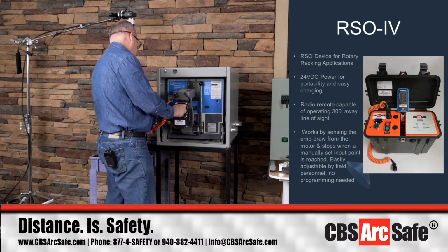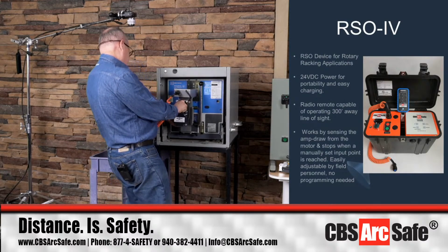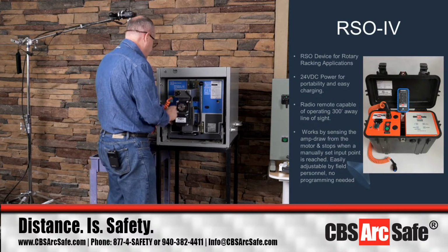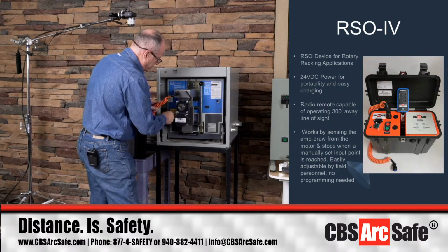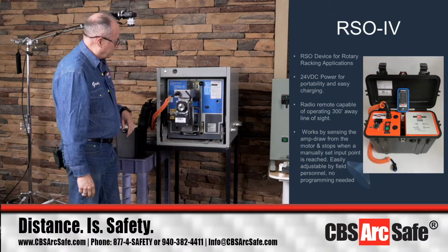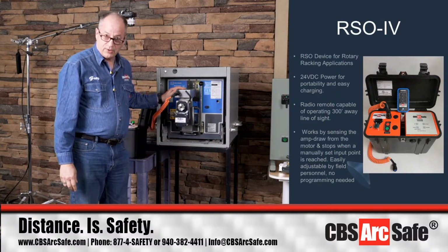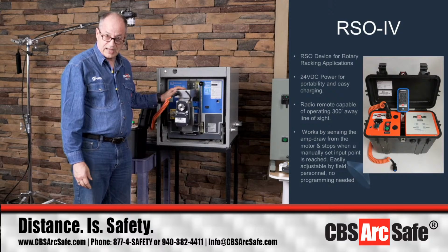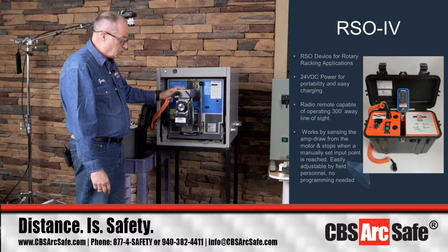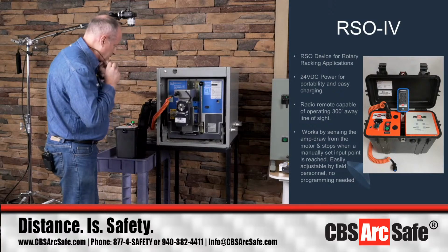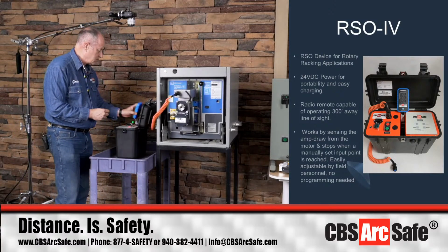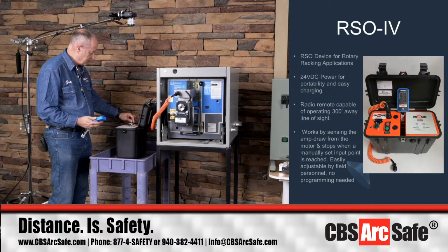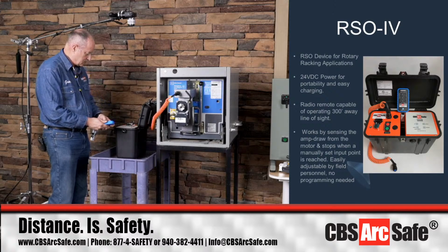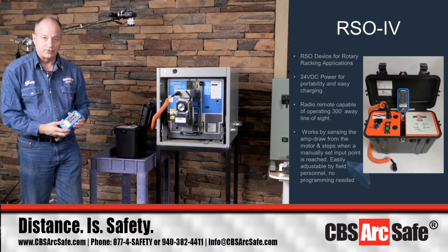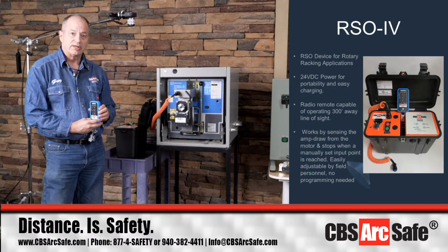Once you've got it situated up here, then what you're going to work to do is index it to get it onto the drive shaft right there, and then just rotate the handle one time. And always make sure you're following your safety rules and that you're going to be outside of the arc flash hazard boundary. While we're doing this in a conference room, if I'm actually doing this with the radio remote now, again, I can do this from up to 100 meters away with a clean radio path.